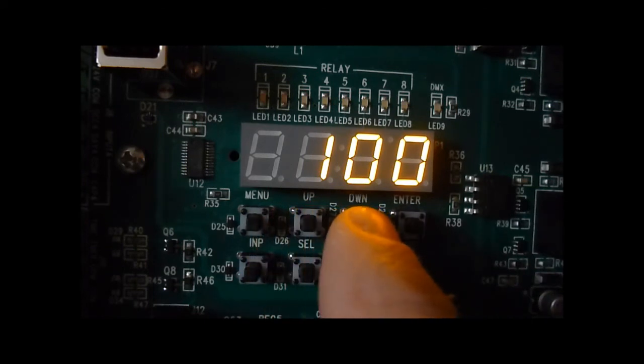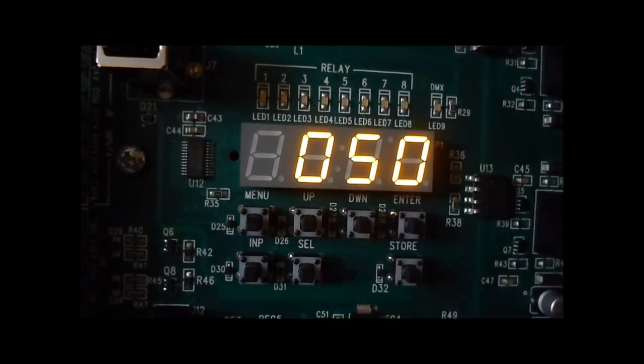A secondary zone, where we want the fixture to provide more light, we could reduce that. So say we'll reduce the zone to 50 percent effect from the daylight sensor. A primary daylight zone will be affected by 100 percent, so the daylight sensor has full control. A secondary zone that's farther away, more artificial light will come from the fixture itself.